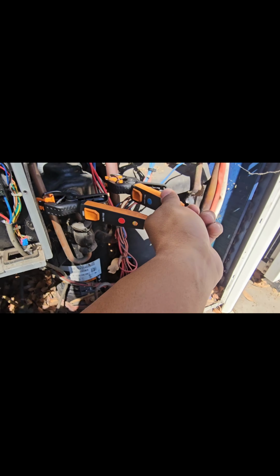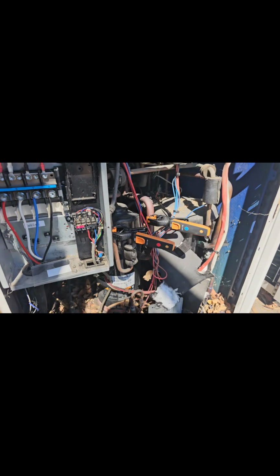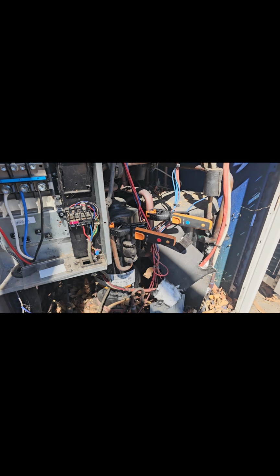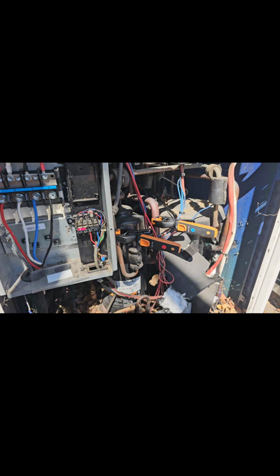I'll put the low on the low, and I will put up a screen recording of the values that I get on these 2 sensors, and you guys can essentially see what's happening over here. Our compressor 2 is running and this line is ice cold. As you can see, we are sweating back, and our suction line temp is 5 degrees and 6 degrees.